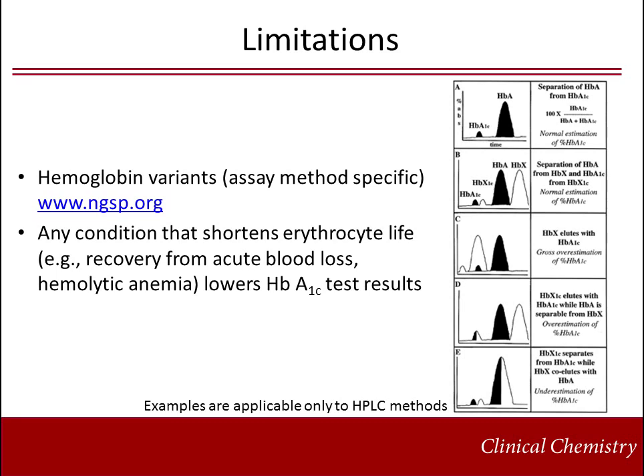Several hemoglobin variants, as well as carbamylated hemoglobin, may interfere with some assay methods independently of any effects due to shortened red blood cell survival. As shown by this slide's hypothetical HPLC analysis, depending on the particular hemoglobin variant and assay method, hemoglobin A1C results can be either falsely increased or falsely decreased. For more information on method-specific interferences of hemoglobin variants, visit the NGSP website. Given that interferences are method-specific, product instructions from the manufacturer should be reviewed before the hemoglobin A1C assay method is used. When selecting an assay method, a laboratory should consider characteristics of the patient population served. If altered red blood cell turnover interferes with the relationship between mean blood glucose and hemoglobin A1C values, or if a suitable assay method is not available for interfering hemoglobin variants, alternative non-hemoglobin-based methods for assessing average glycemia, such as the fructosamine assay, may be useful.